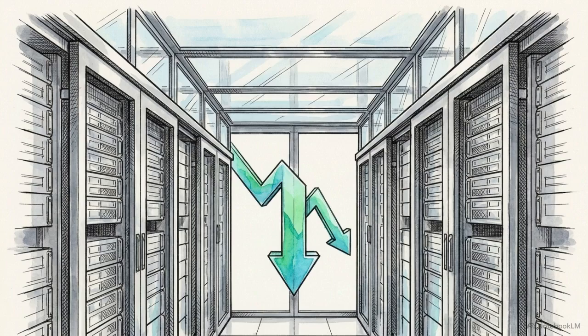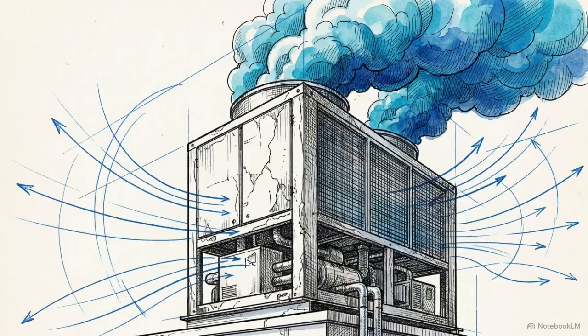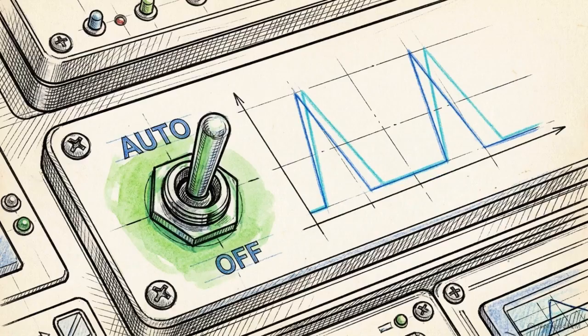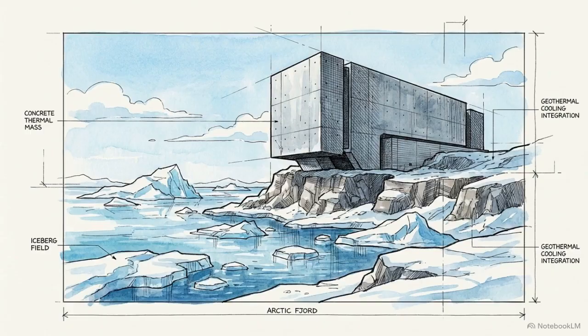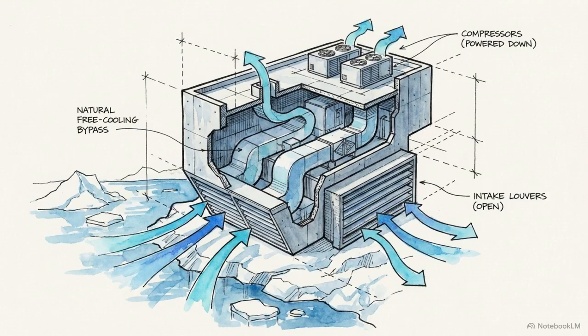The next engineering hurdle is control. Running huge industrial compressors at maximum capacity all the time is wasteful, so facilities have to operate them only when mathematically necessary. One major strategy is free cooling. By building data centers in freezing climates or next to deep bodies of water, facilities can pull in natural outside air or local water to chill the building, bypassing the need for power-hungry mechanical compressors entirely.